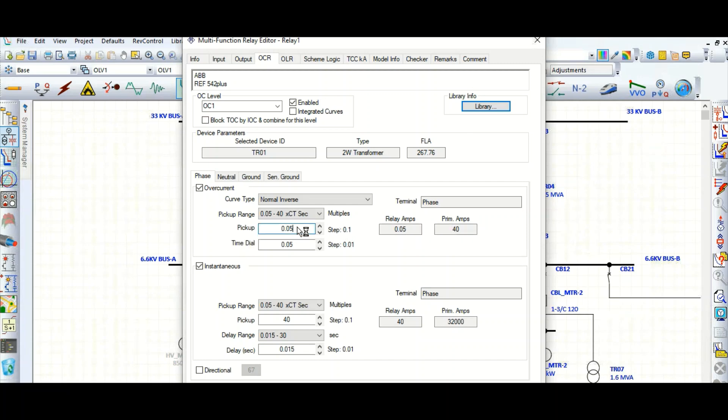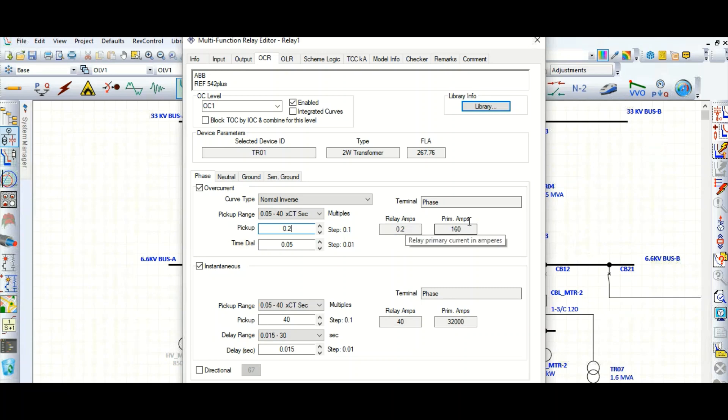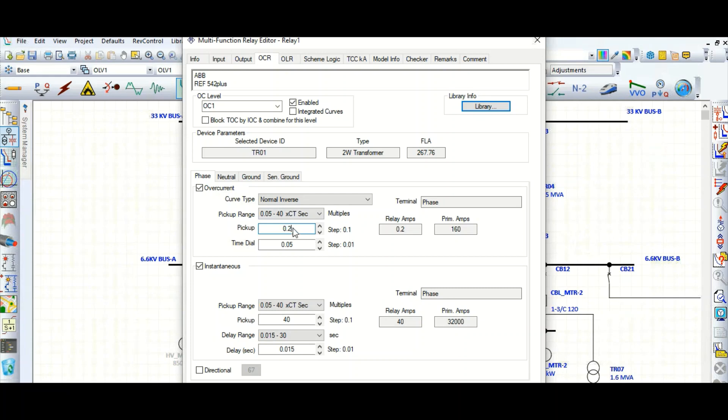So 800 multiplied by 0.05, it will come 40 amps. If you change this pickup, let's say 0.2, so relay amps settings 0.2, so primary current is required 160 ampere required to pick up this relay.